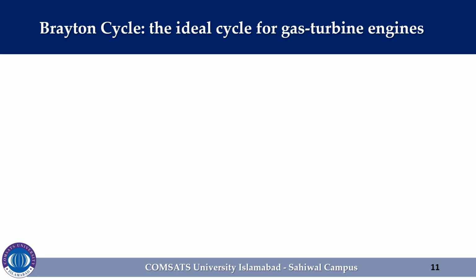Now we will talk about the functions of air in gas turbines and applications of gas turbines. The air in gas turbines performs two important functions. It supplies the necessary oxidant for the combustion of the fuel, and it serves as a coolant to keep the temperature of various components within safe limits. In gas turbines, an air-fuel mass ratio of 50 or above is not uncommon. Therefore, in a cycle analysis, treating the combustion gases as air does not cause any appreciable error.